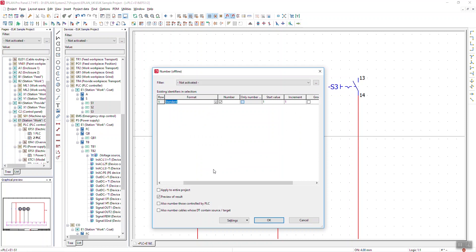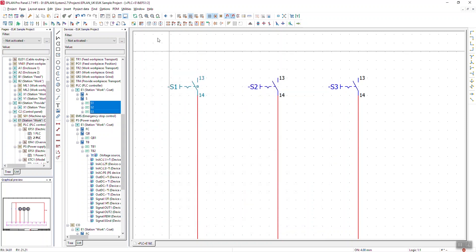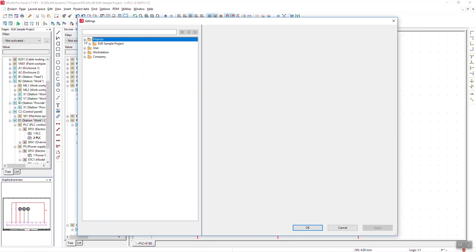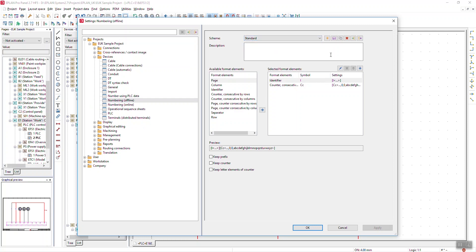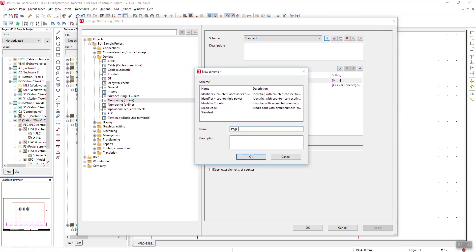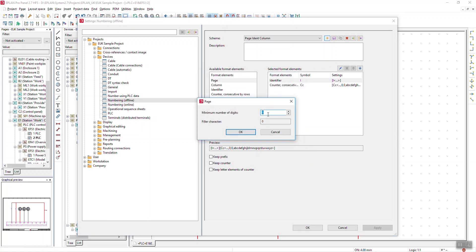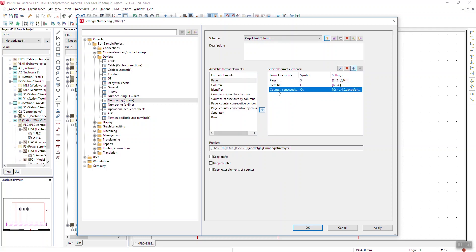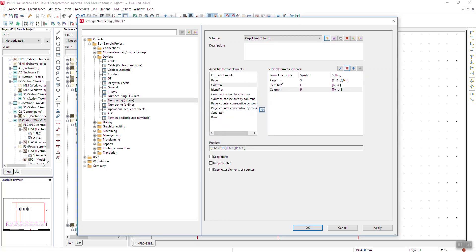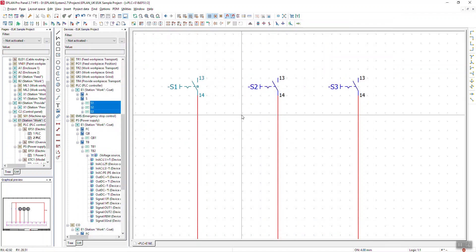I can go into Options > Settings, then into my project settings under Devices > Device Numbering Offline. Here I can make a new scheme. I might want Page + Identifier + Counter, or Page + Identifier + Column — different ways of doing it. I select Page, with a minimum number of digits of two, so on page one you get 01, page two you get 02, and so on. Above my identifier I've got Column, so I don't need a counter. I click Column, set the minimum number of digits to zero, giving me Page + Identifier + Column. I click OK and now have a new scheme.